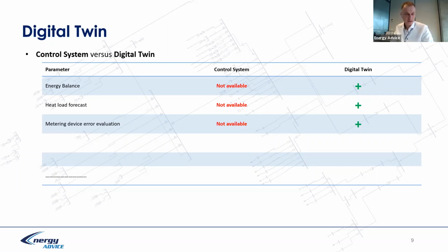For example, oxygen level. Oxygen in flue gas meters, day by day, hour by hour, need to be cleaned because the measurement error increases, and the digital twin understands that the measurement error increases. However, the control system controls air supply to the furnace according to this oxygen level, so the increased error impacts the control system's measurement and its decisions. And we can put in other variables we should monitor.